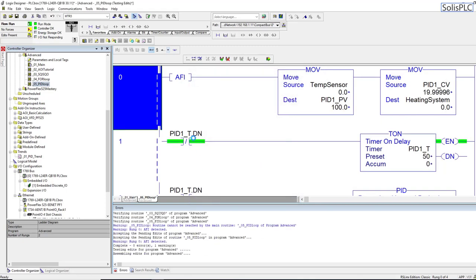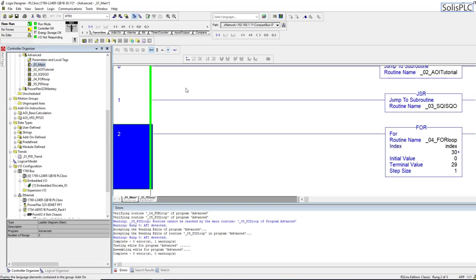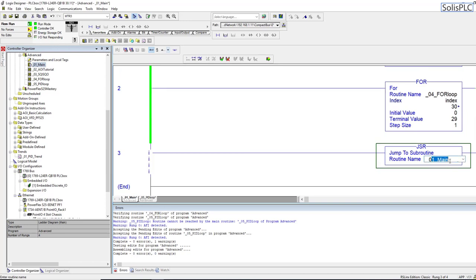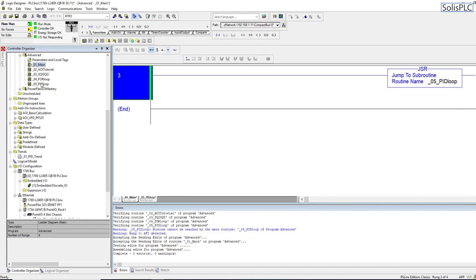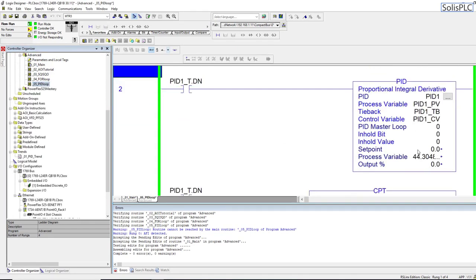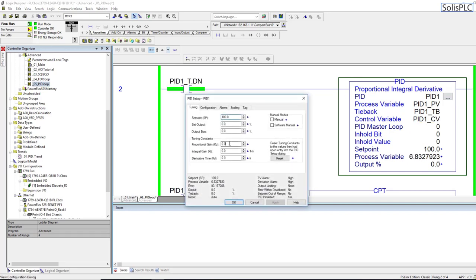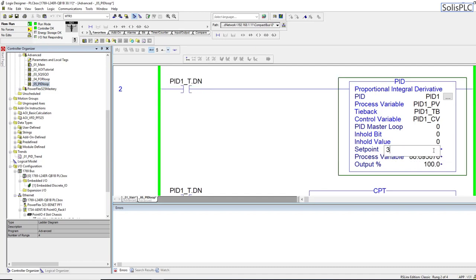We need to go back to main and call this routine using a jump-to-subroutine instruction, referencing the PID loop routine we just created. Since the set point is zero the process variable will go down, so I'll set it to 100 and give some random gain values of 5. After hitting apply and OK, you can see the output is at 100 and the process variable is trending towards the set point.